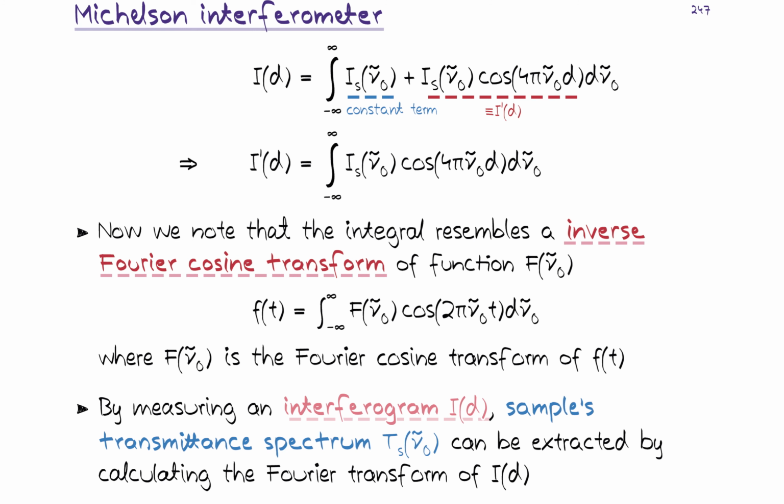And the nice thing why there are devices known as FTIR spectrometers, so Fourier transform infrared spectrometers, is that by doing measurement using this, we can reduce the amount of noise quite substantially, especially when we are operating at the longer wavelengths. And when we are trying to measure light at the longer wavelengths, hence the IR part in the FTIR, the detectors that can be used are inherently quite noisy.